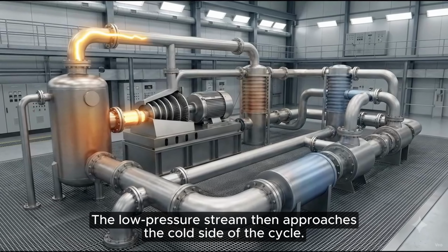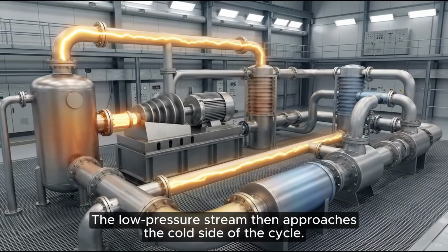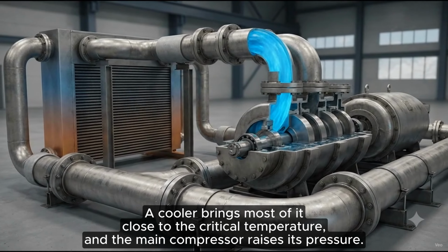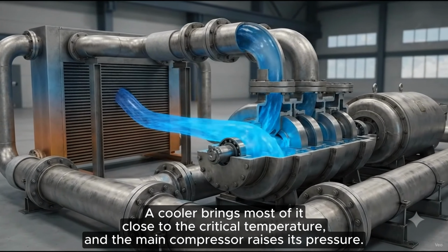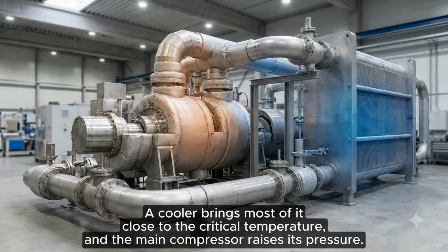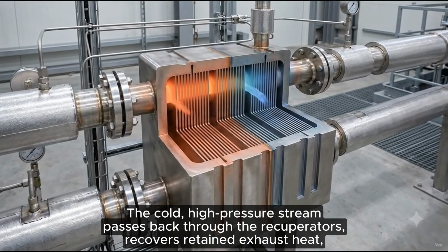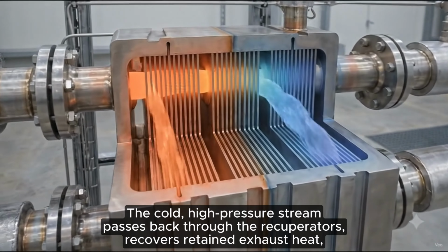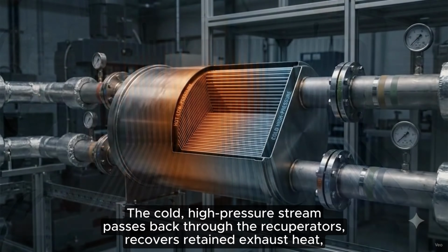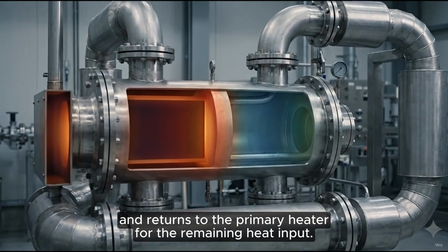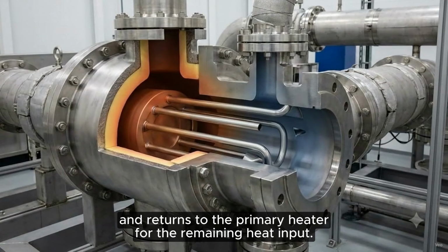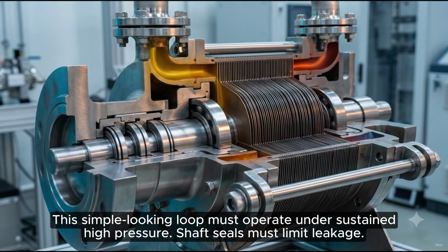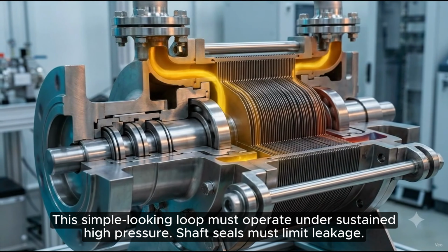The low-pressure stream then approaches the cold side of the cycle. A cooler brings most of it close to the critical temperature, and the main compressor raises its pressure. The cold, high-pressure stream passes back through the recuperators, recovers retained exhaust heat, and returns to the primary heater for the remaining heat input. This simple-looking loop must operate under sustained high pressure.